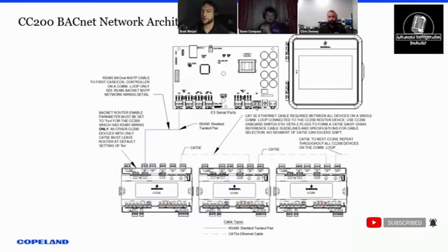Is there a difference whether you're on Cat 5 versus just daisy chaining them together with a regular communication cable? Yeah. So the preliminary goal number that we're striving towards was for Cat 5 to get to that 100 on one network, one strand. Now, if we were doing RS-485, we can do 32 per port, and then you can stretch that across multiple ports to get up to 90 or however many cases you have in the store.